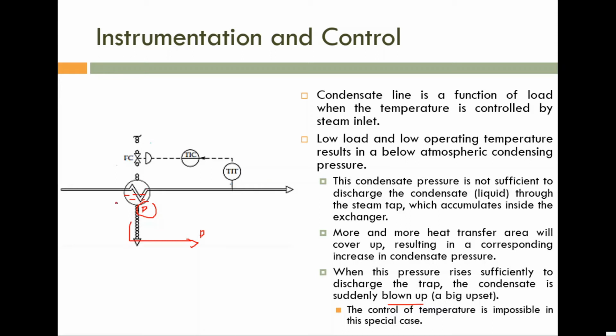And what is the second problem? The liquid level inside this pipeline and this heat exchanger is increased, so the liquid head will increase. With the increase of liquid head, at a particular point, that liquid head is sufficient to remove this liquid from this point to the next point. After some time, the liquid head is increased, so the pressure is increased. That pressure is sufficient to remove the entire liquid that is trapped inside the pipeline and the heat exchanger to the next point.